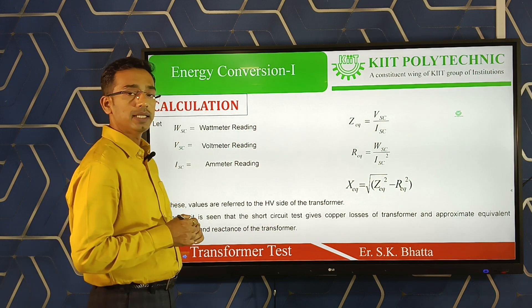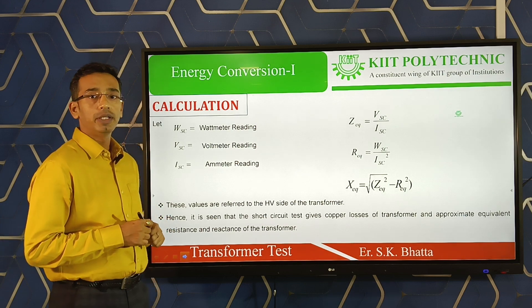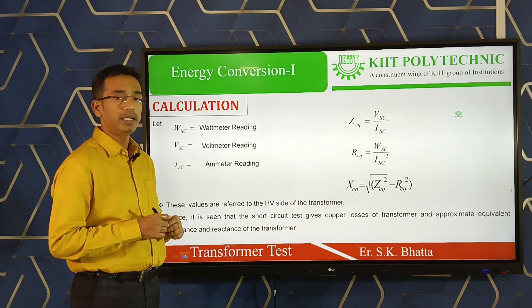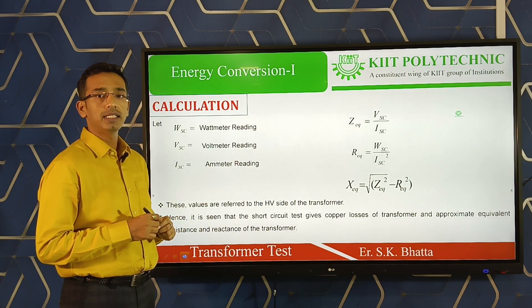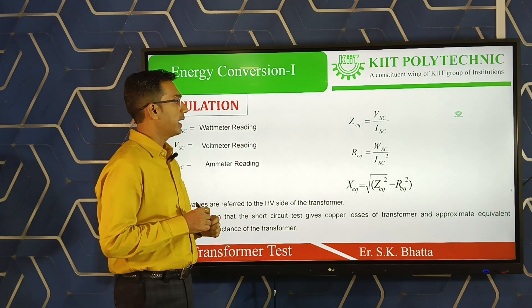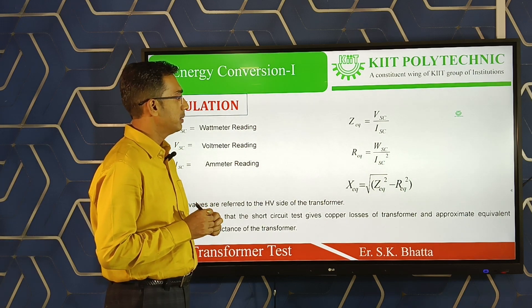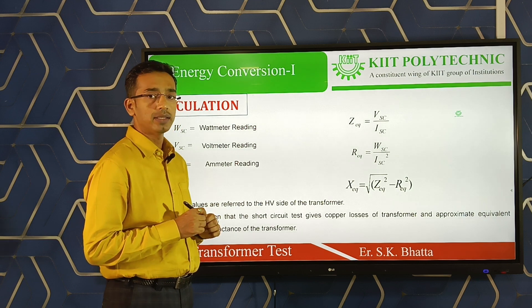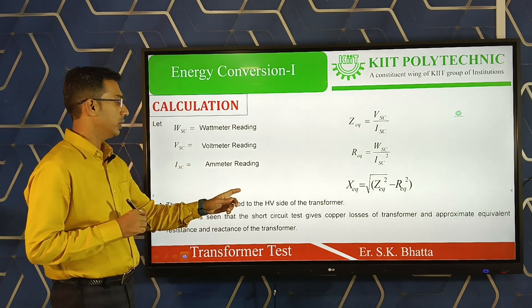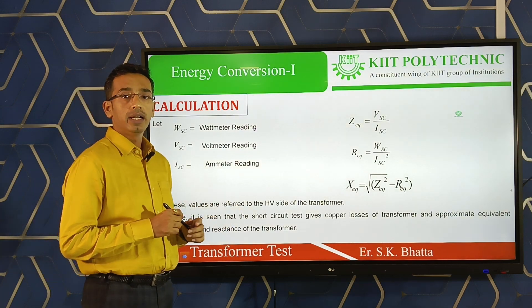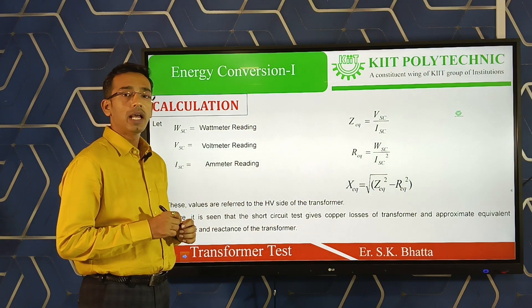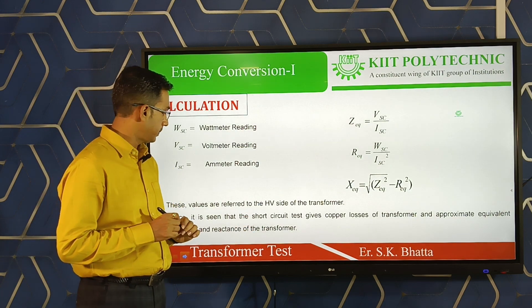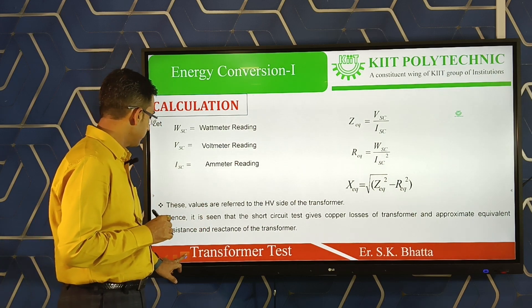For short circuit test calculations: Wsc is the wattmeter reading, Vsc is the voltmeter reading, and Isc is the ammeter reading. The equivalent impedance Zeq = Vsc / Isc. The equivalent resistance Req = Wsc / Isc². The equivalent reactance Xeq = √(Zeq² − Req²). These values are referred to the HV side of the transformer. Thus the short circuit test gives copper loss and equivalent circuit parameters.